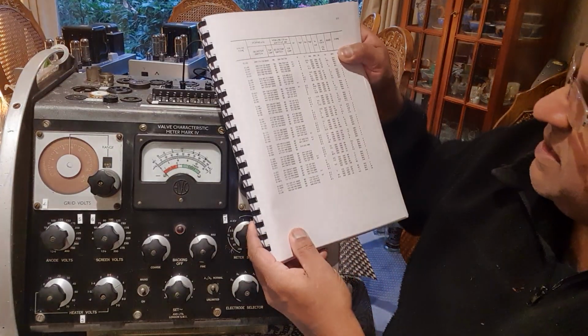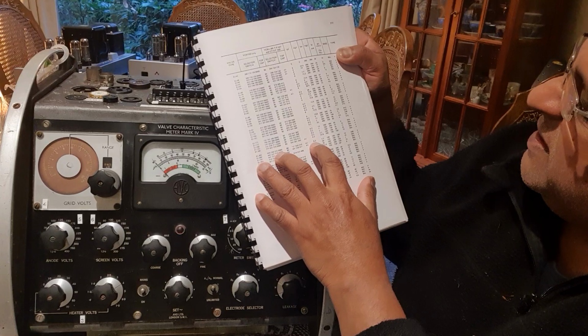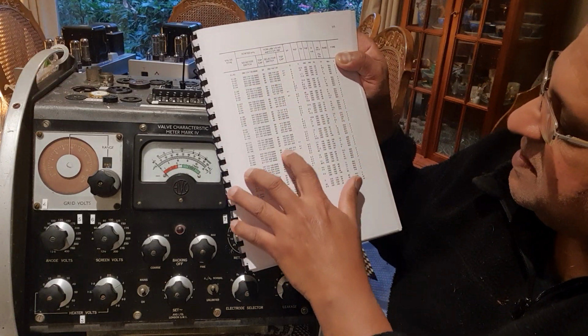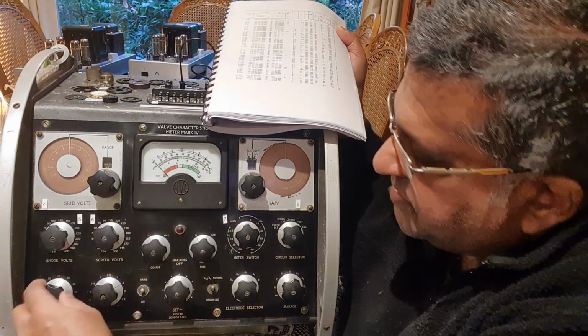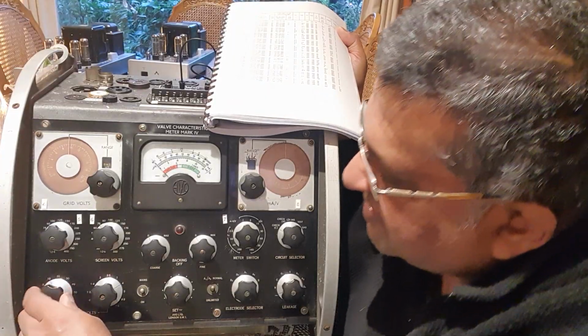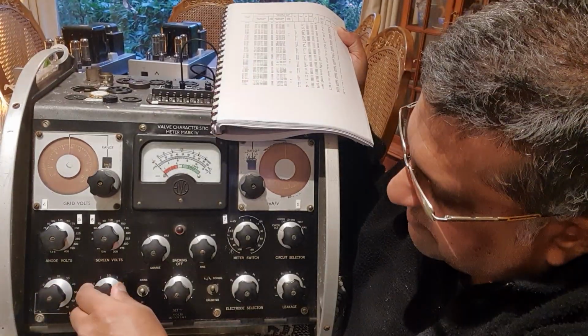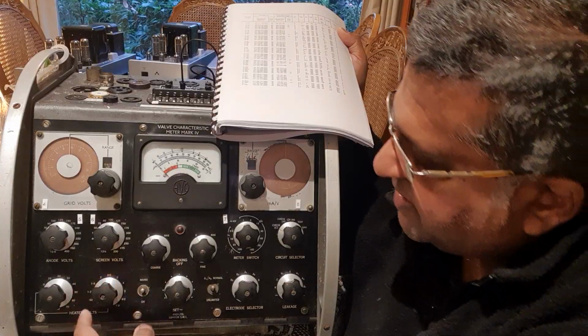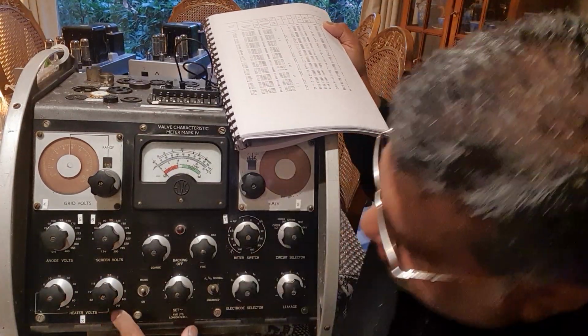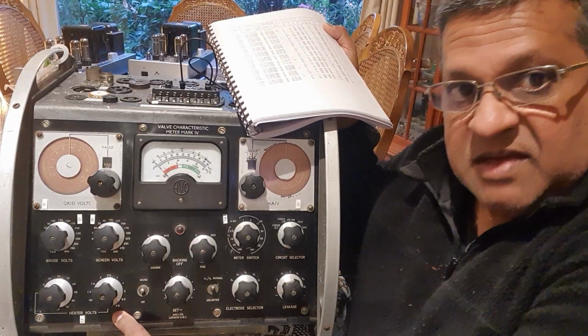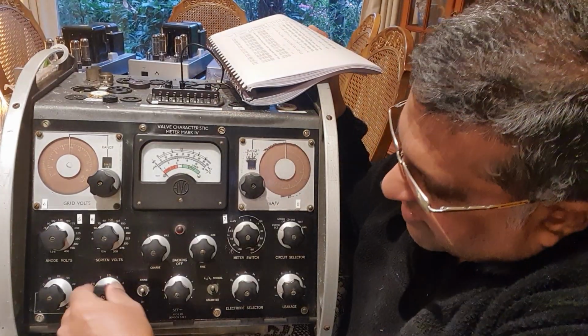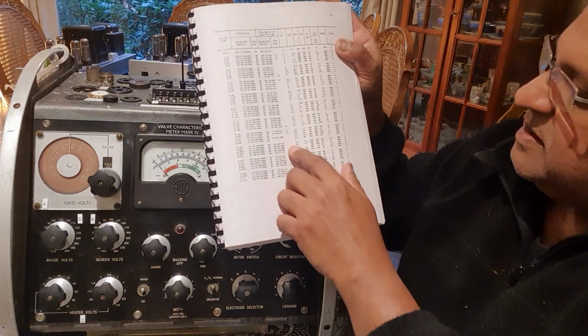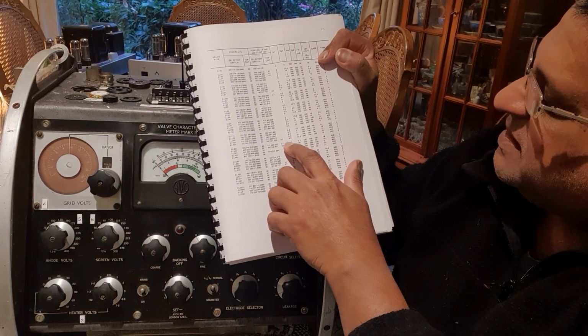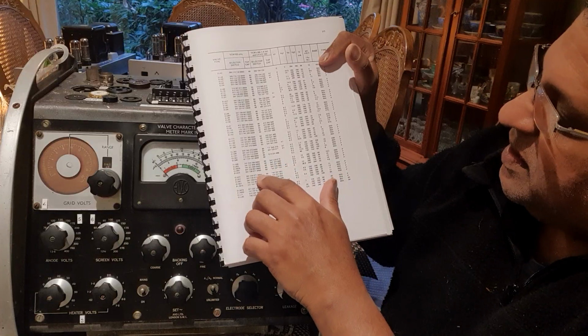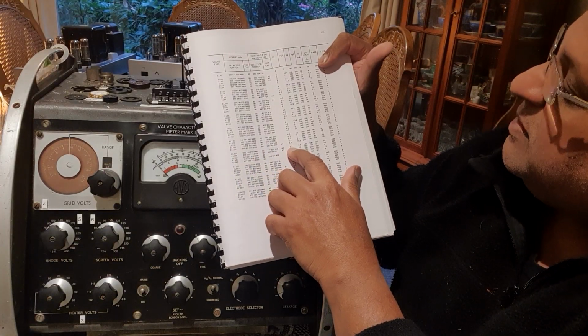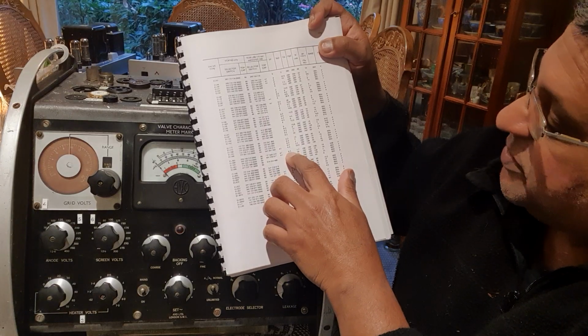Now, the voltage for the element, heat element, is 6.3. So I'm going to set it to 6.3. This knob is in the increment of 10, so this has to be 0 because this one is between 0 to 7.5 volts. So I would be setting this one up to 6.3 because of the valve for EL, the heat element. The voltage for heat element is 6.3.